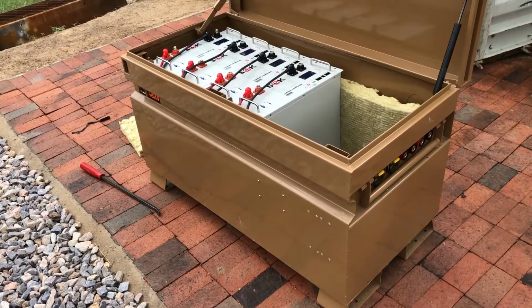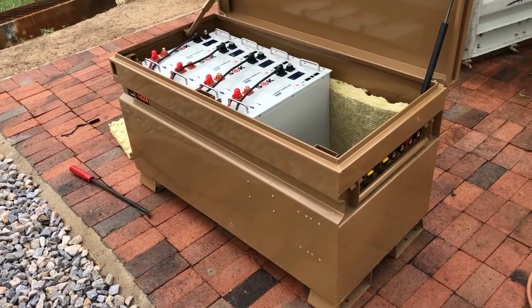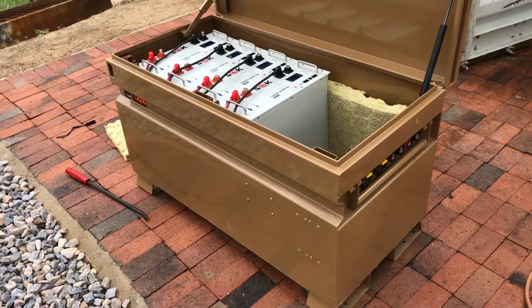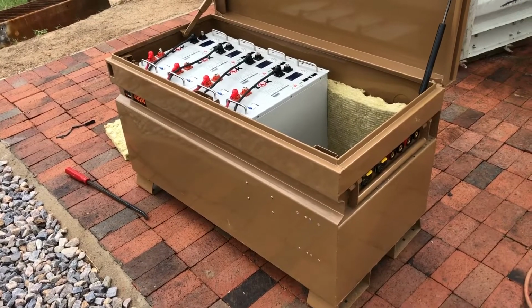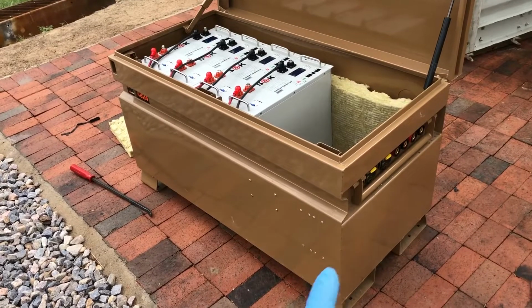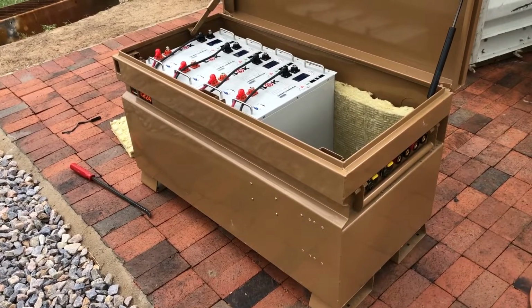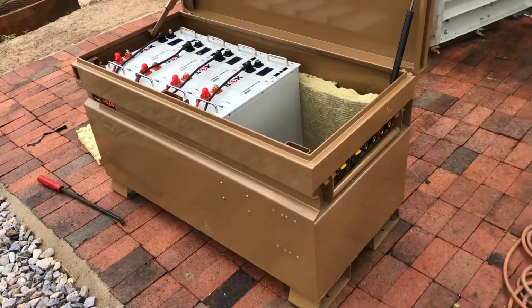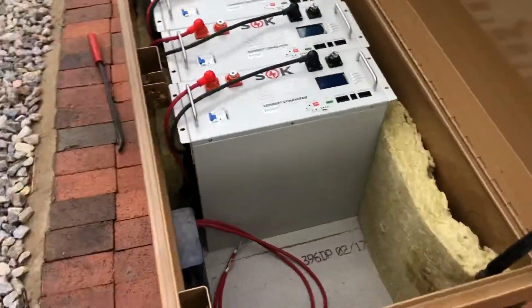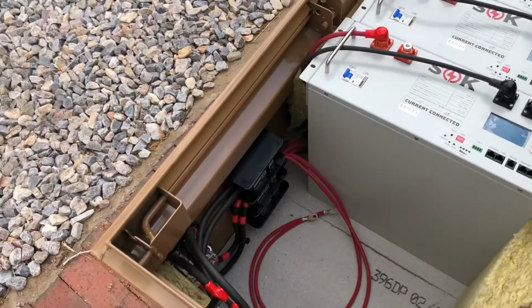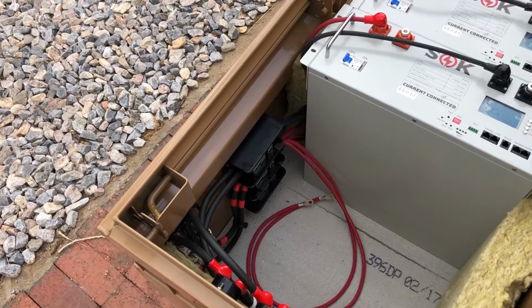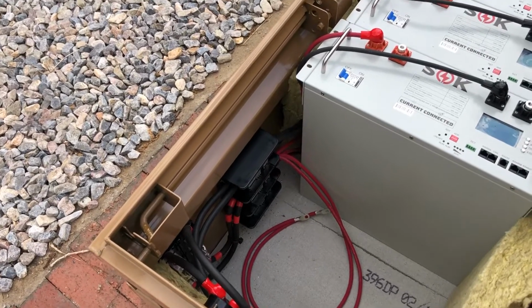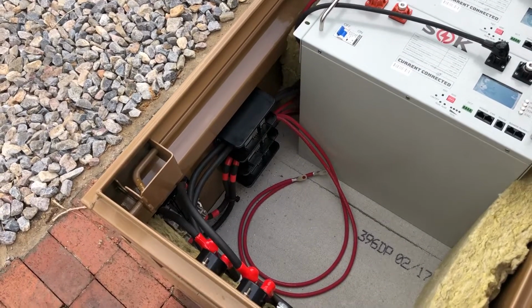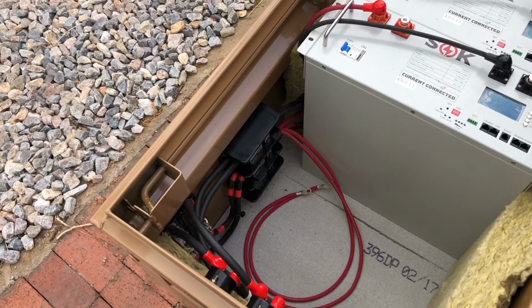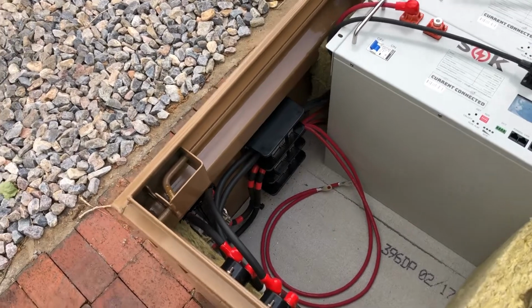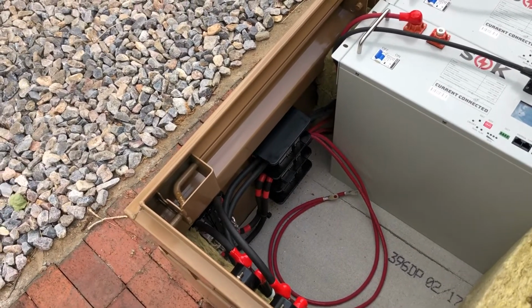That would be less great if I had nuisance tripping of the breaker, and a lot worse if I blew those fuses. I really think those should be 300 amp fuses, because you really don't want those to go first. So I'll see how this goes, and if I have to change them for 300, I will.